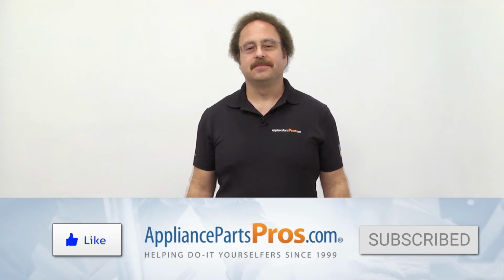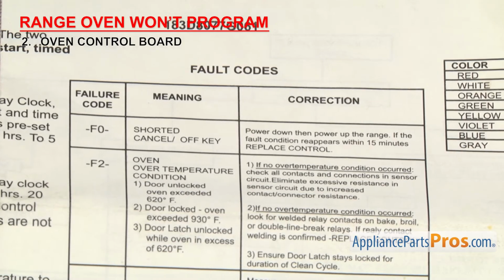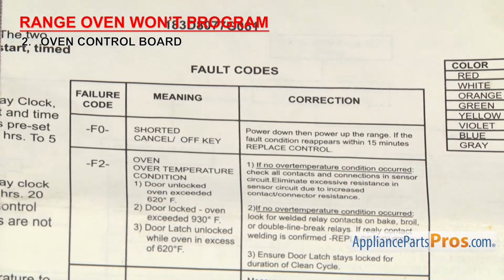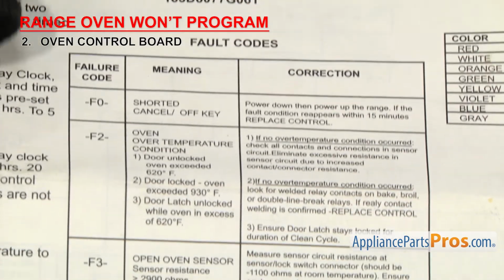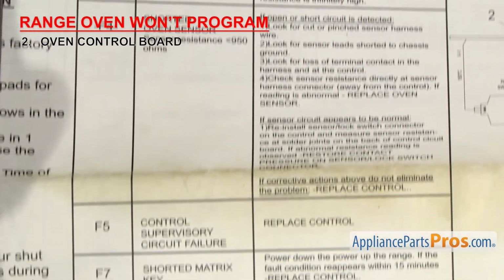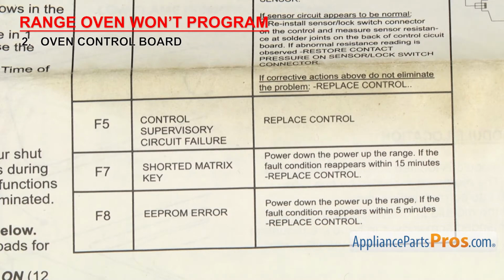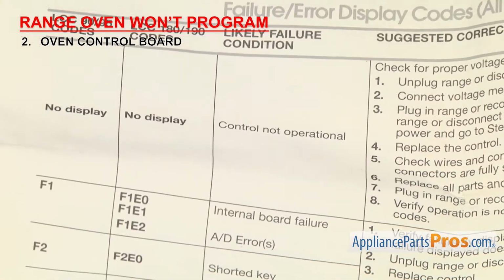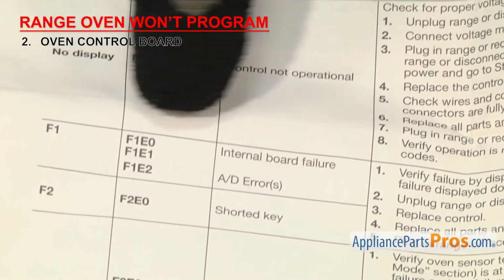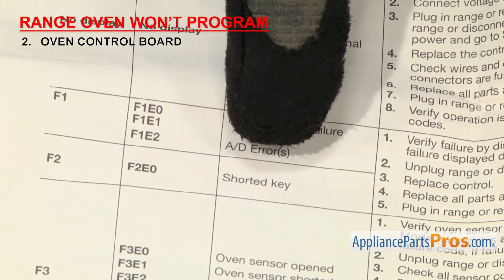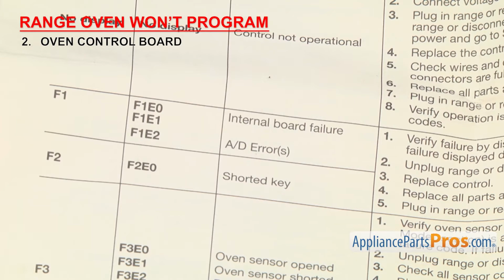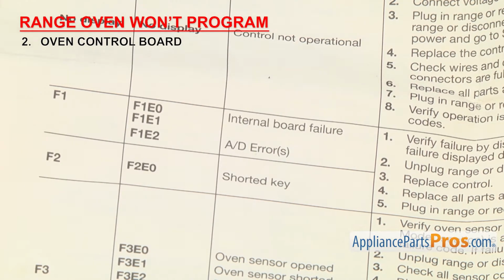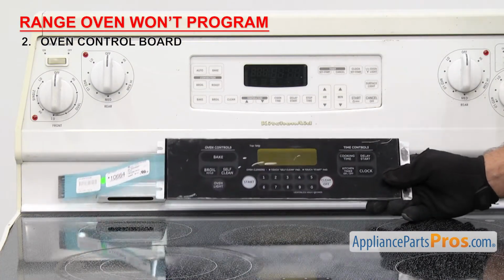There are a lot of different control boards out there, so we can't show you how to test them all. You're going to have to grab your tech sheet and follow the diagnostics or error codes to see if it's gone bad. In this example, if the display is dead, it would indicate a bad control board and you should just go ahead and replace it. If it's not dead, it could be giving you an error code showing that the board has failed or has a stuck key.